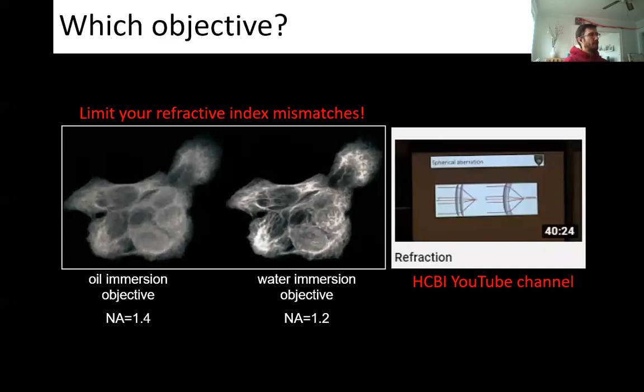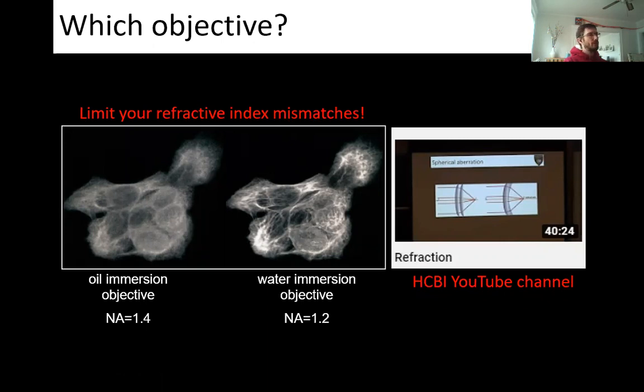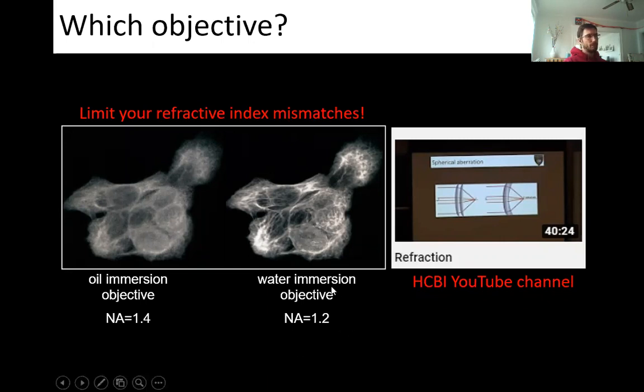Regarding objective choice — remember what refractive index your sample is in. A live sample in media is in a refractive index similar to water, around 1.33. Using an oil immersion objective with oil at refractive index 1.52 will cause severe spherical aberration and significant signal loss. In that situation, a water immersion objective, a silicone oil immersion objective, or one with a correction collar is much better. For more detail, watch the refraction video on our YouTube channel from a previous lunch-and-learn.